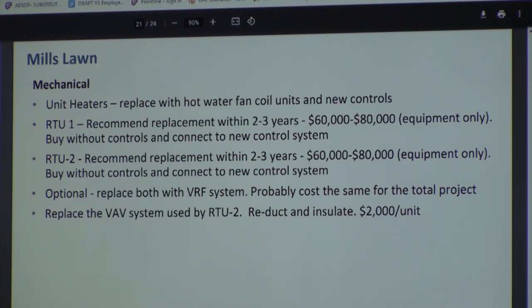It is an option to replace those units with VRF. That's a pretty good application for a VRF system. If you wanted to do that, it would probably be more expensive at the end of the day than going back with rooftop units. The VAV boxes are about $2,000 with controls, or about $1,600 without controls. So you'd have to replace those. I think there's 19 of them. I don't remember, so.